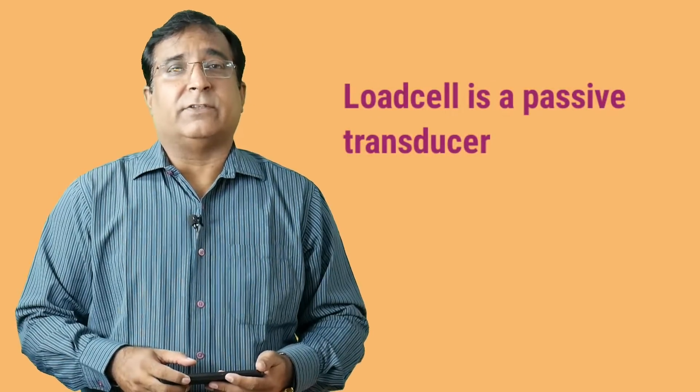Now the load cell is no longer an active transducer. That means it does not produce any voltage or current signal on its own like thermocouple does. It is passive transducer. So you need to apply an external voltage to measure the change in resistance. Now this voltage is called excitation voltage.